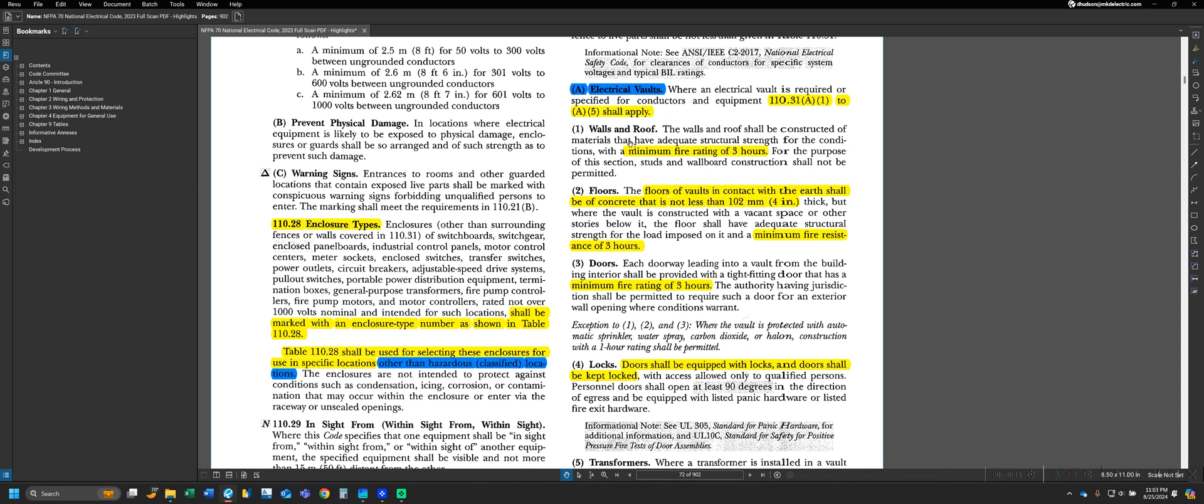We can see that for the walls and roof, they have to be constructed of material that has adequate strength for the conditions and has a minimum fire rating of three hours. We can see that any doors that lead into the vault have to be provided with a door that has a minimum fire rating of three hours. We can see that the floors of the vault, if they're in contact with the earth, have to be concrete, not less than four inches thick, or otherwise it has to have a minimum fire resistance of three hours.